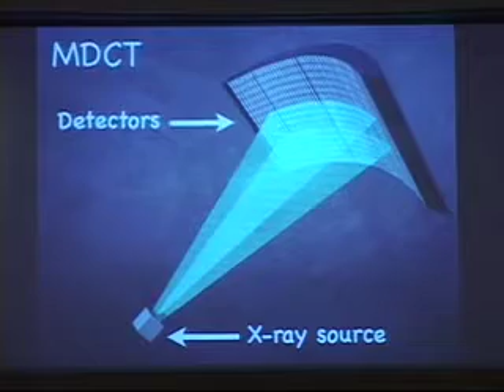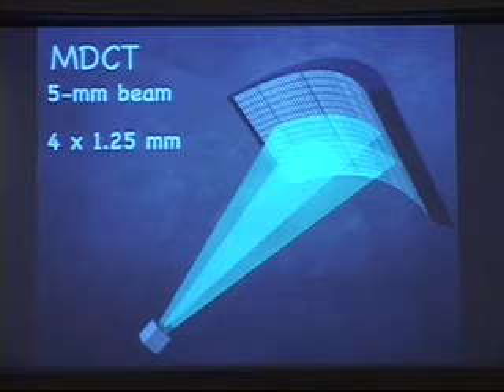Each of these is 1.25 millimeters in thickness, and so with a 5 millimeter beam, we would then simultaneously acquire 4 1.25 millimeter thick sections. When we highlight the entire width of the detectors, depending on the type of CT scanner we have, if we have a 4-row scanner, then we will group these detectors into groups of 4, having 4 5 millimeter clusters.